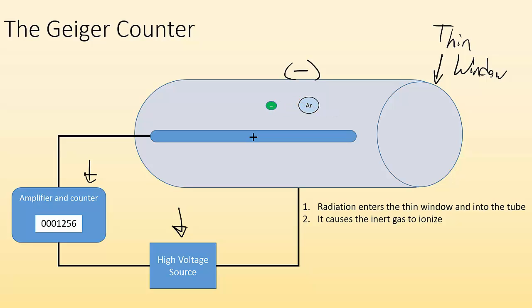It causes the argon gas to become ionized. And now that we have charged particles, and we have these electrodes that are charged, we'll get some migration of those charged particles. So the charged particles migrate towards the anode and towards the cathode. You get the negative going towards the positive terminal, and the positive argon moving towards the negative terminal. Now, what just happened is a movement of charge, and the movement of charge is an electrical current. So we just completed the circuit, and we got a charge. We were able to detect a current.